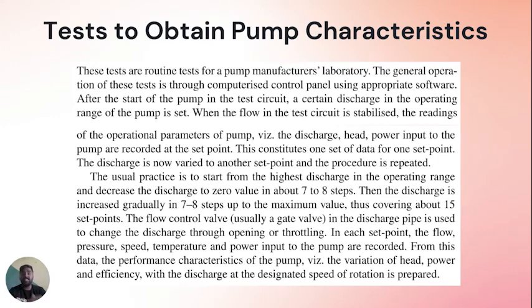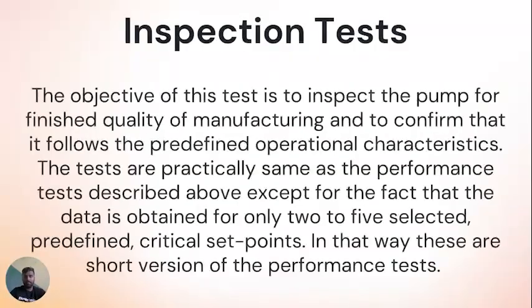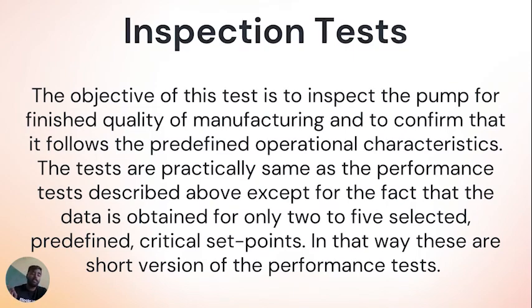Several tests to acquire pump characteristics are routine tests for pump manufacturer labs. After starting the pump in the test circuit, a certain discharge in the operating range is set; when flow is stabilized, readings of discharge, head, and power are recorded — this constitutes one data set for one set point. The discharge is then varied and the procedure repeated. Inspection tests confirm finished quality of manufacturing and predefined operational characteristics, obtaining data for only two to five selected critical set points — short versions of the performance tests.